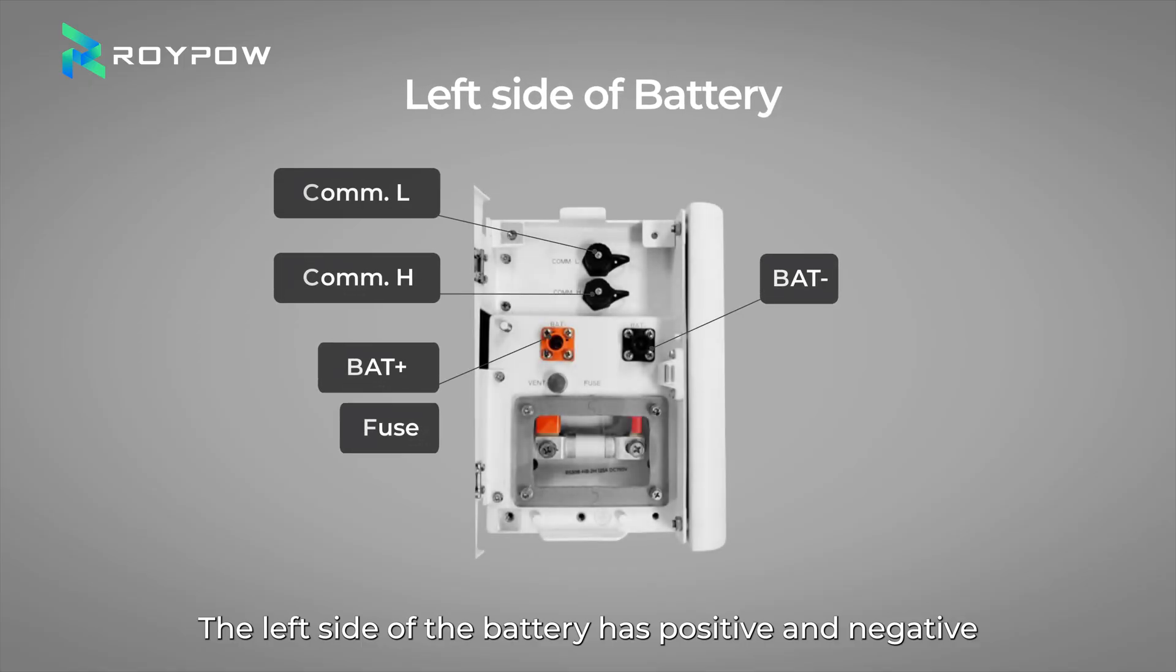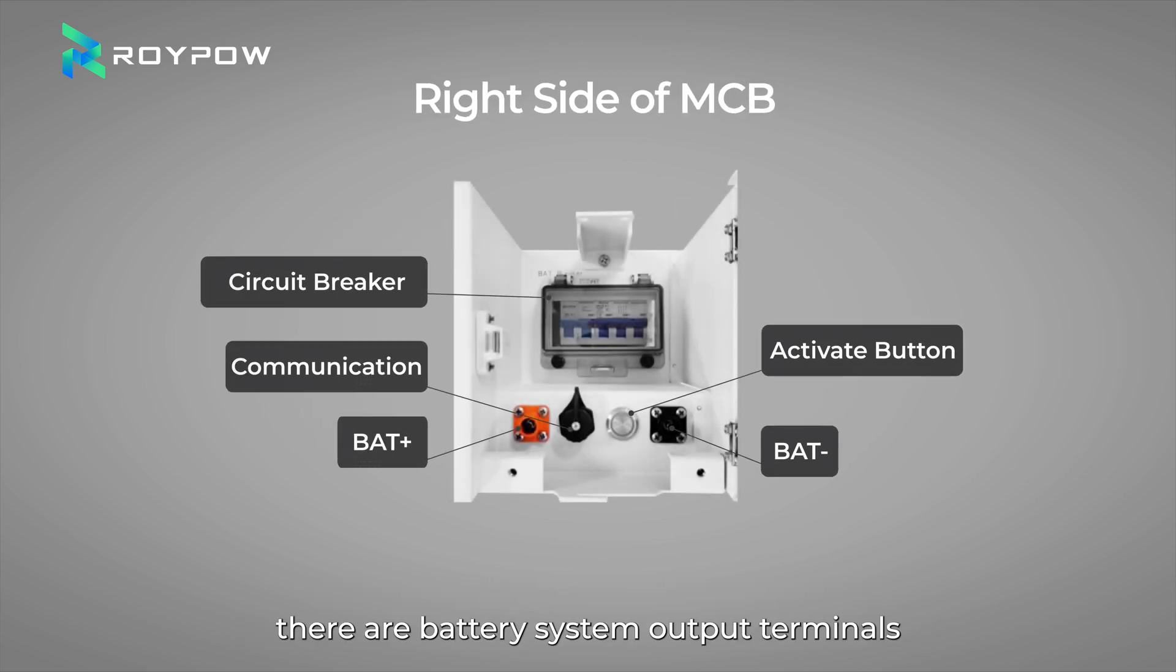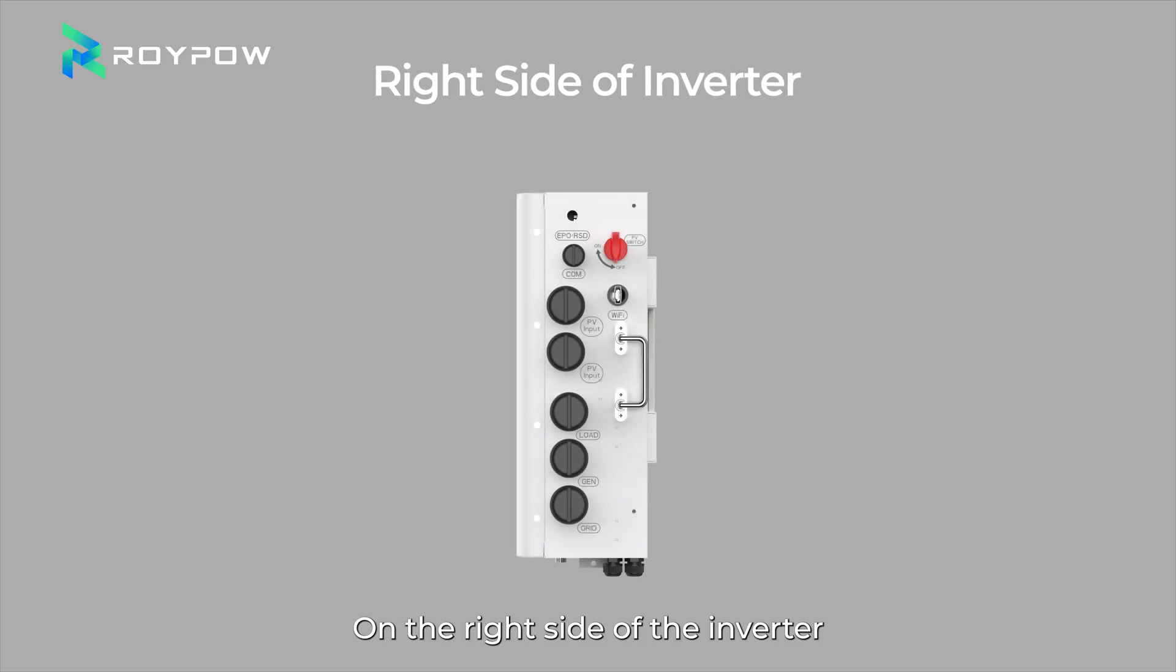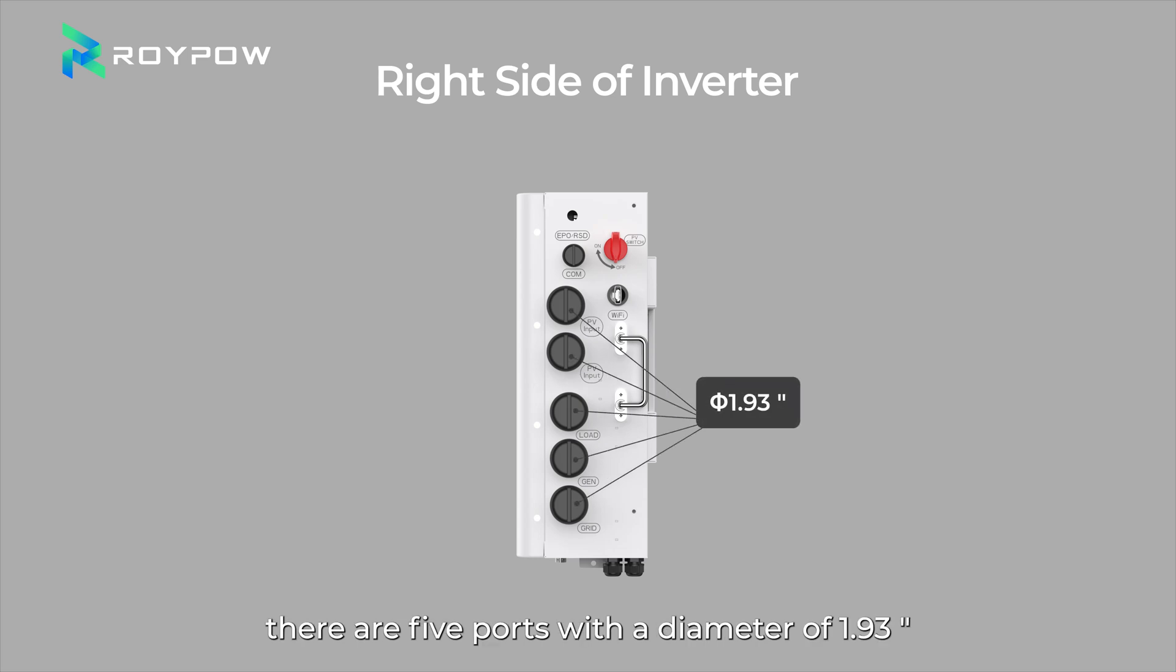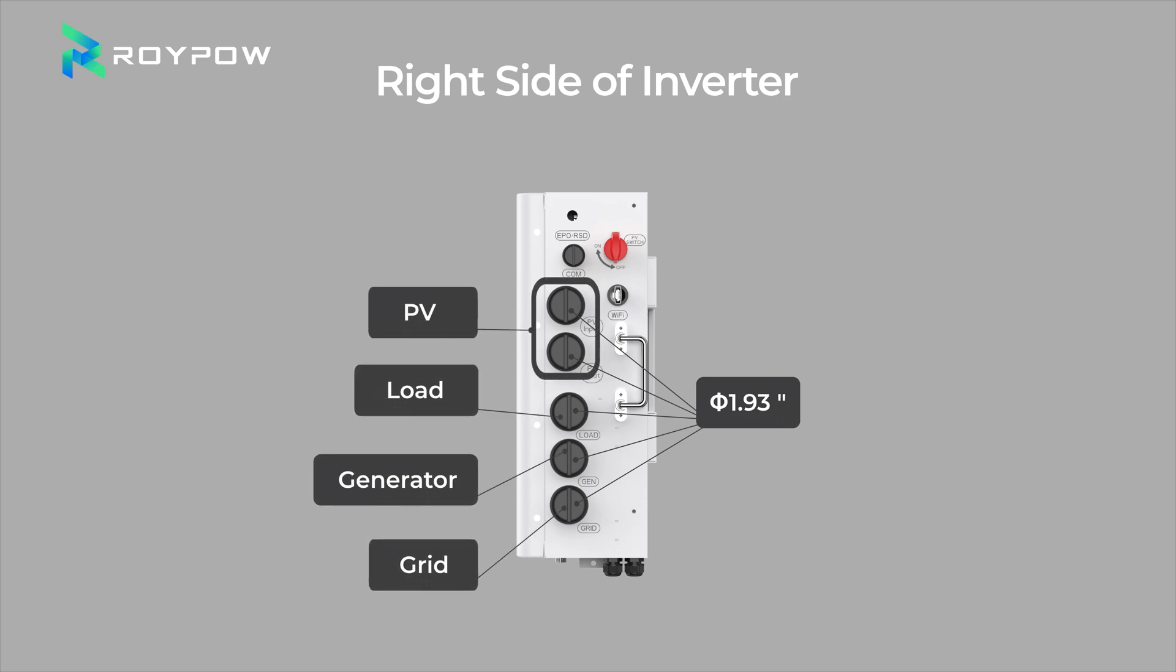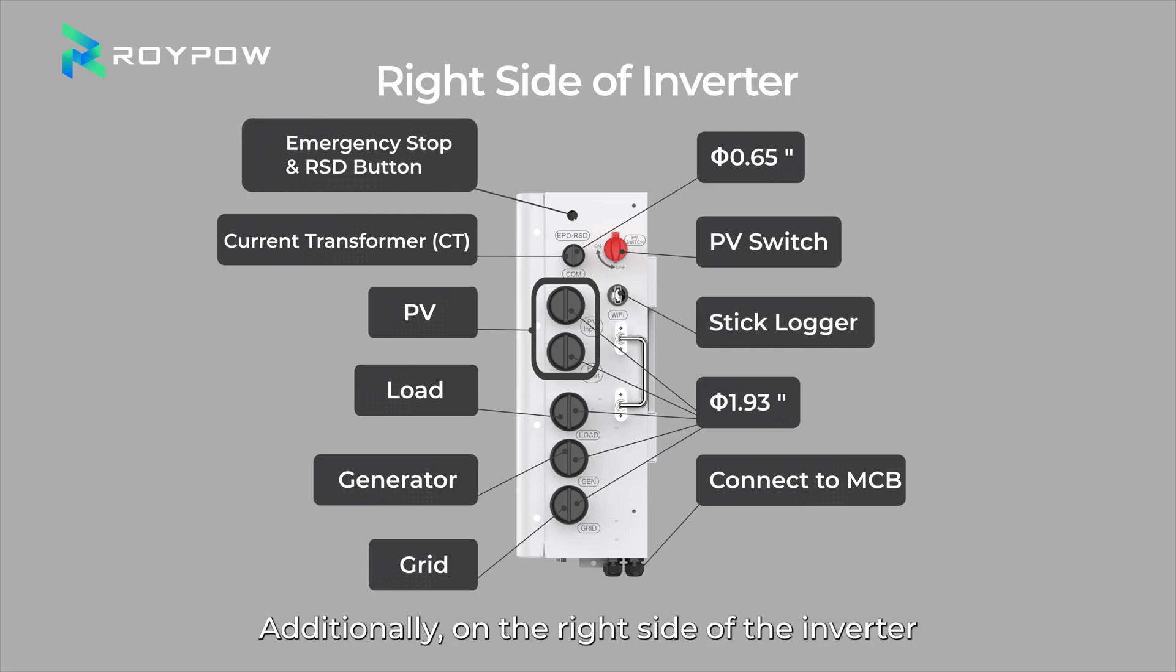The left side of the battery has positive and negative battery output terminals and communication interfaces. On the left side of the main control box, there are battery positive and negative input interfaces and communication interfaces. On the right side of the main control box, there are battery system output terminals, a communication interface, a switch button, and a circuit breaker. On the right side of the inverter, there are 5 ports with a diameter of 1.93 inch, which are used for PV, generator, grid, and load. There is also a 0.65 inch port for CT connection. At the bottom of the inverter, there is a pair of positive and negative cables for connecting to the main control box. Additionally, on the right side of the inverter, there is an RSD switch, a PV switch, and a stick logger interface.